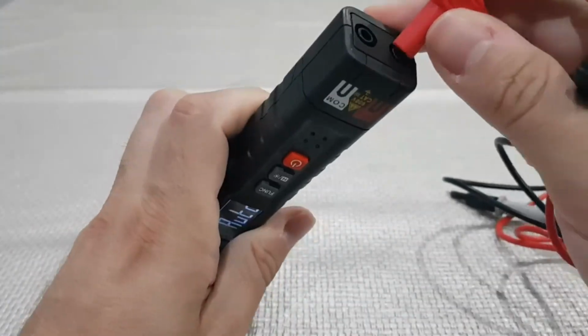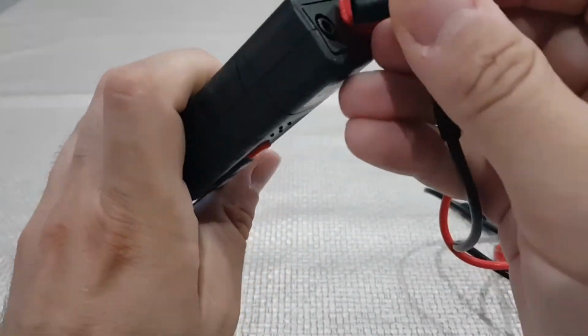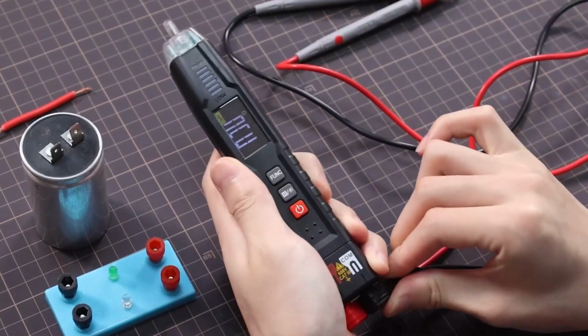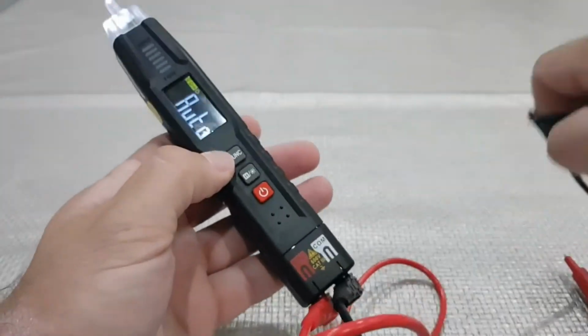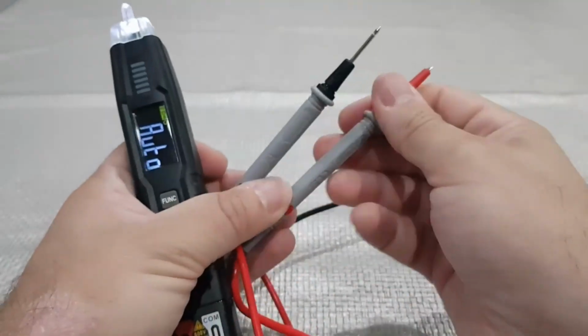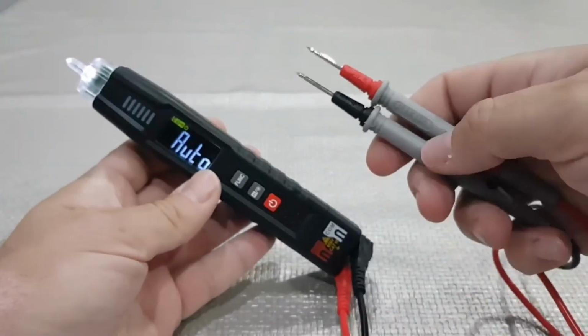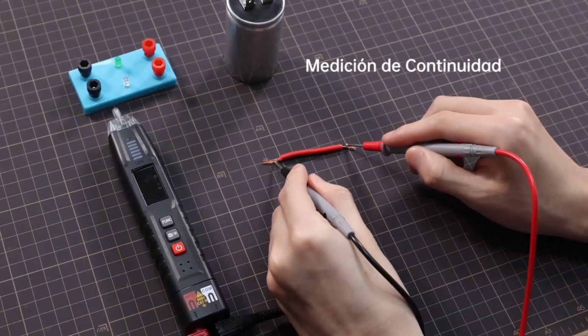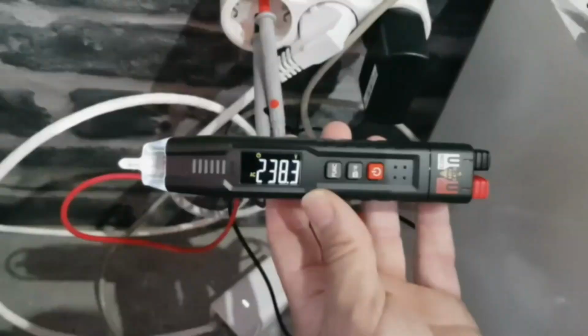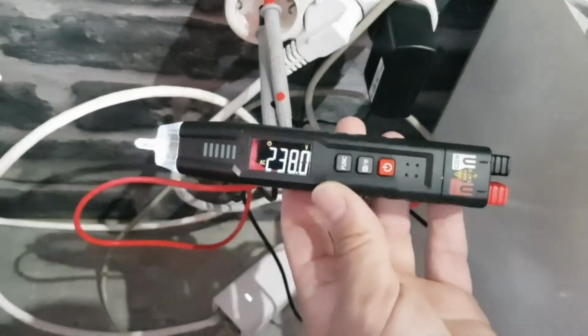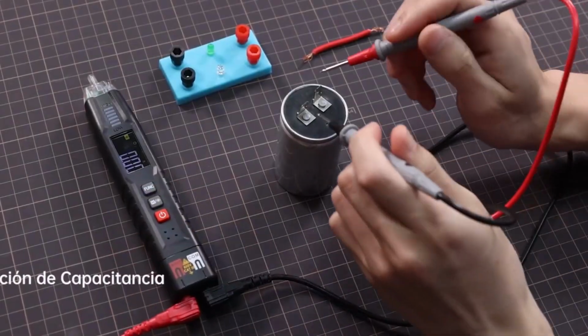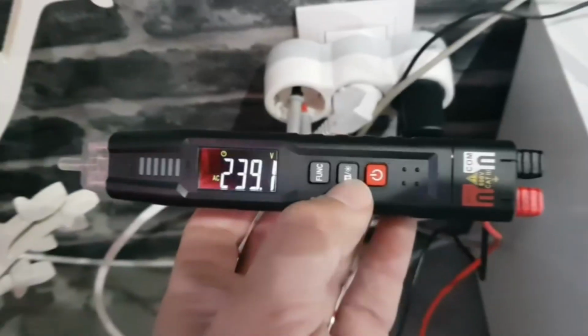This is the tool for the HVAC engineer, the lift installer, and anyone climbing to awkward places all day. Think about an air conditioning unit on the roof of a commercial building. Hauling a full-size bench meter up there is a nuisance, while this slides into a shirt pocket and lets you confirm supply at the motor and measure the start capacitor. Against the Venlab, you trade the laser and the tough build for real measurement ability, which for fault finding is a different game entirely. Auto mode takes a couple of seconds to decide what it's looking at, so racing through continuity checks on a board calls for a slower hand. The feature nobody expects is phase sequence. Commissioning 3 phase motors or pumps, confirming rotation before you press start saves you a very expensive afternoon.